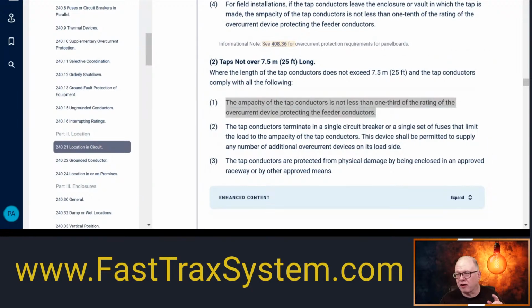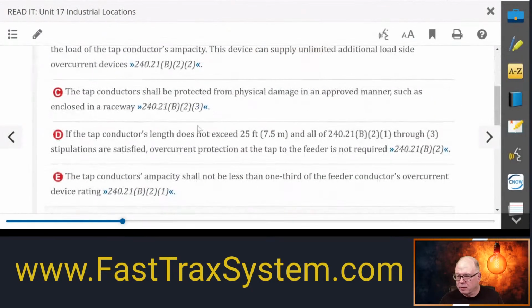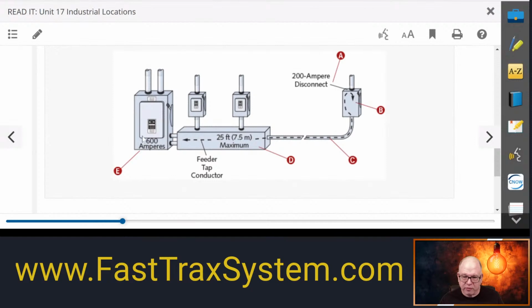So let's go back to our example here. This is 600 amps. So this feeder conductor can't be less than 1/3 of this rating. This one's easy. 600 divided by 3 is 200. So the ampacity can't be less than 200 amps. So it looks like probably a 3/0 copper, right? All right, so let's go on to the next one.